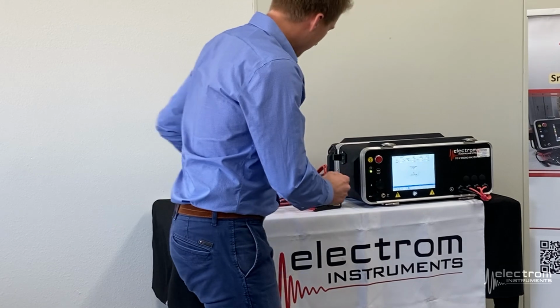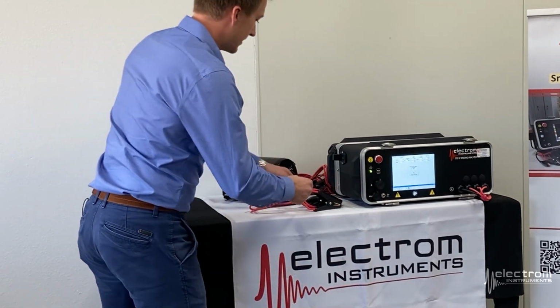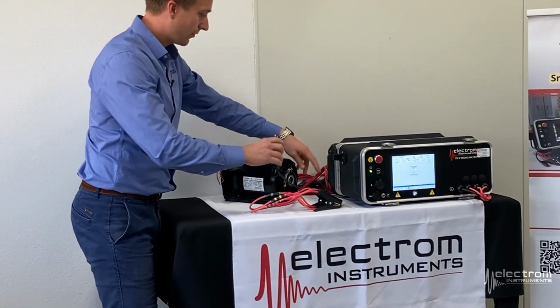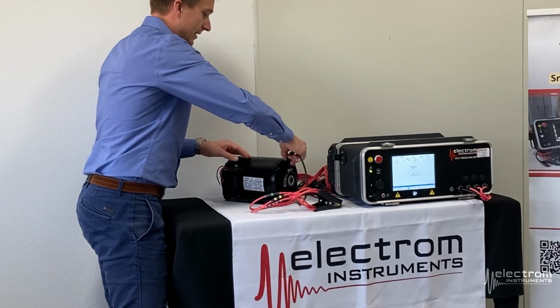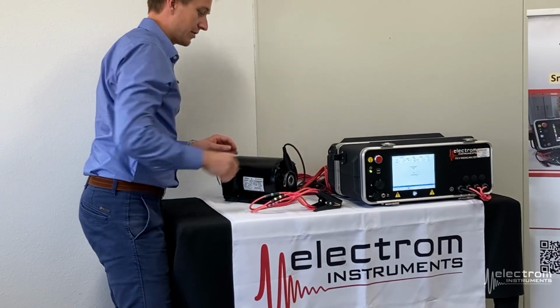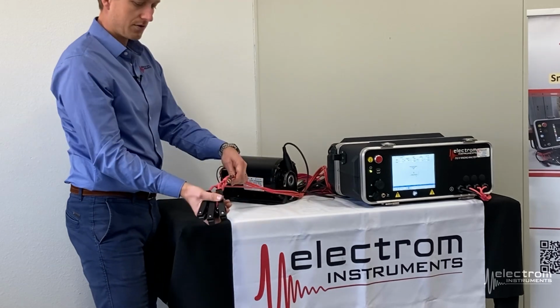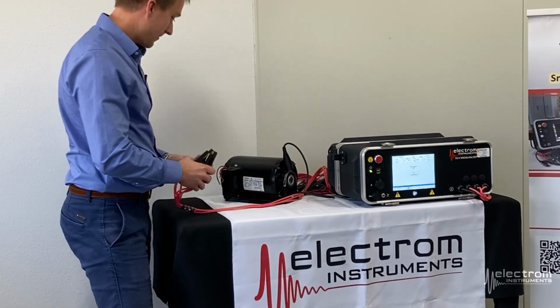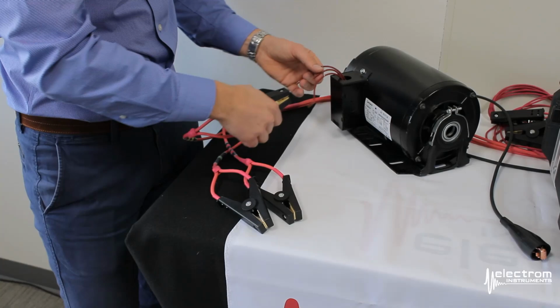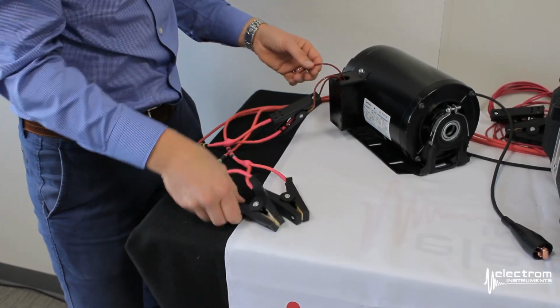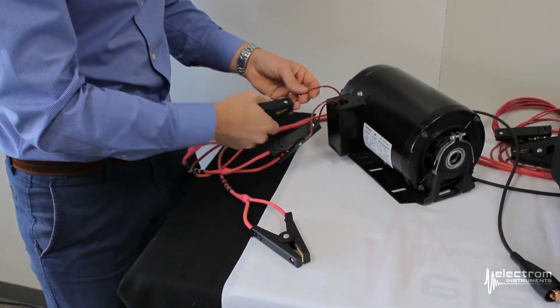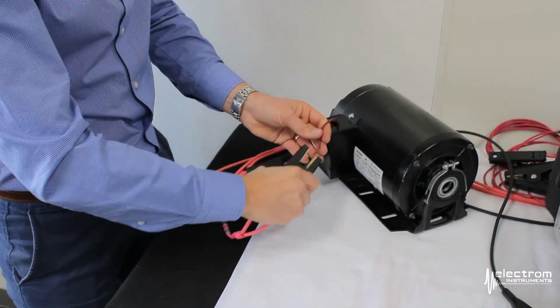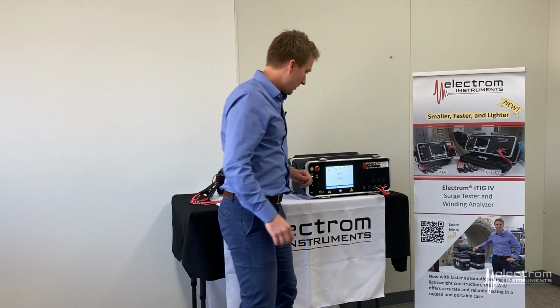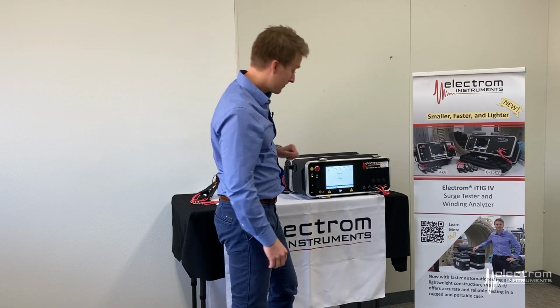So first step here is to connect the test leads. So ground clip to the frame of the motor, unpainted clean surface to make sure we have good contact. Lead 1, 2, and 3 to phase 1, 2, and 3. Like so. And then we are ready to start the test set.